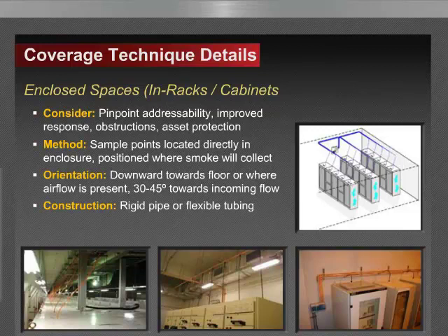So most electric and electronic components will degrade over a long period of time with observable telltales that can be sensed by aspirating incipient smoke detectors designed and installed to detect within the enclosure. So this method involves placement of the sampling points directly into the enclosure and positioned where smoke will collect. This may be at the top of the cabinet or perhaps side or bottom or mechanically ventilated.